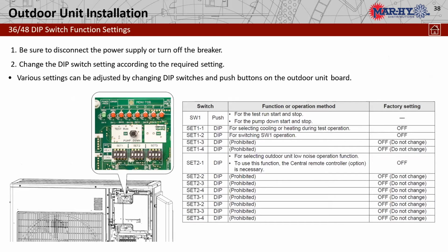Outdoor unit settings. On the 3 and 4 tons, there are a set of control dip switches and a push button switch 1. Those would be pretty much not used. The only reason we would do that would be for a test operation or pump down. If we were doing a pump down operation, we would switch to either heat or cool mode, which is switch set 1, number 1, switch heat, switch cool, and number 2 would give us the ability to use during the pump down operation. And then you would push the switch number 1, the button, to start that. That's if you're doing a recovery mode or something like that. So basically, we really don't need to do anything on that outdoor unit unless you need to do a pump down function.